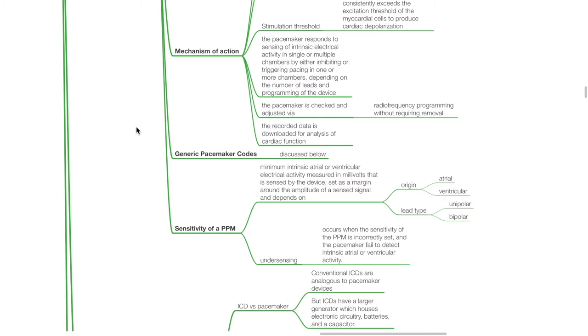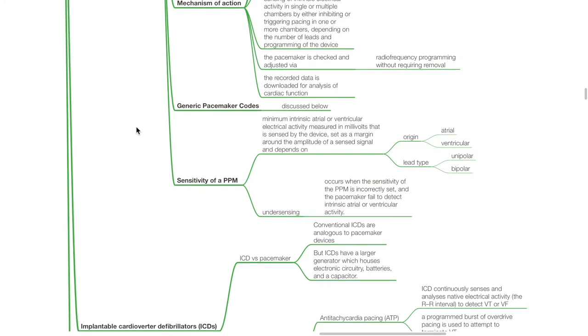Generic pacemaker codes will be discussed in the section below. Sensitivity of a pacemaker refers to the minimum intrinsic atrial or ventricular electrical activity measured in millivolts that is sensed by the device, set as a margin around the amplitude of a sensed signal, and depends on the origin — atrial or ventricular — and the lead type — unipolar or bipolar.